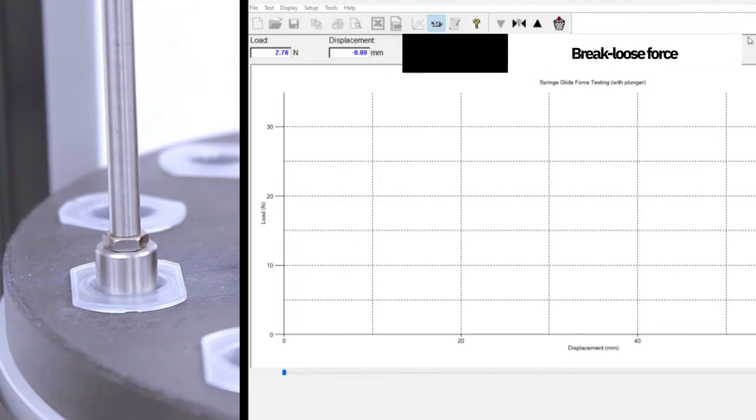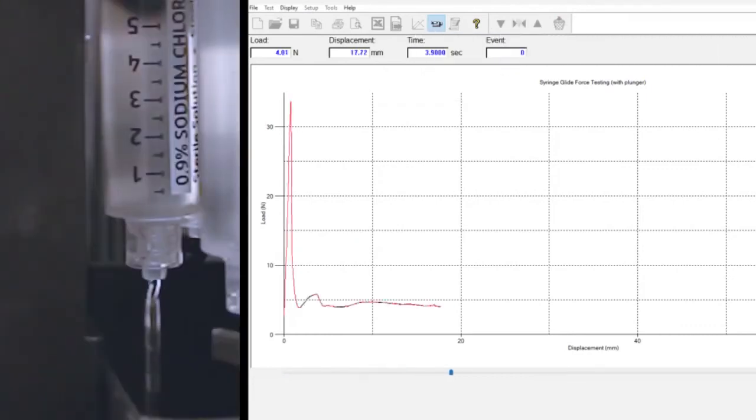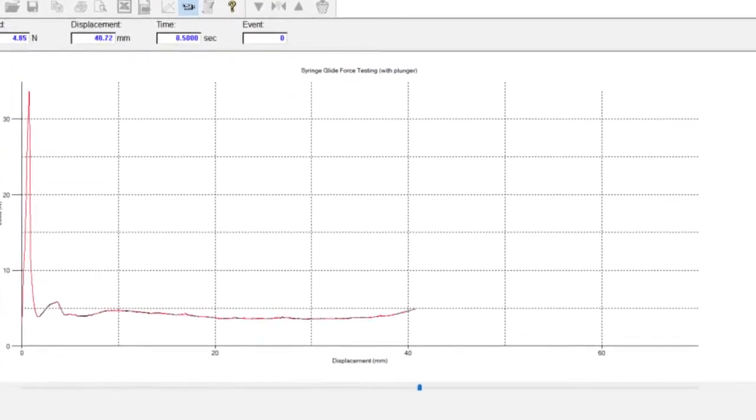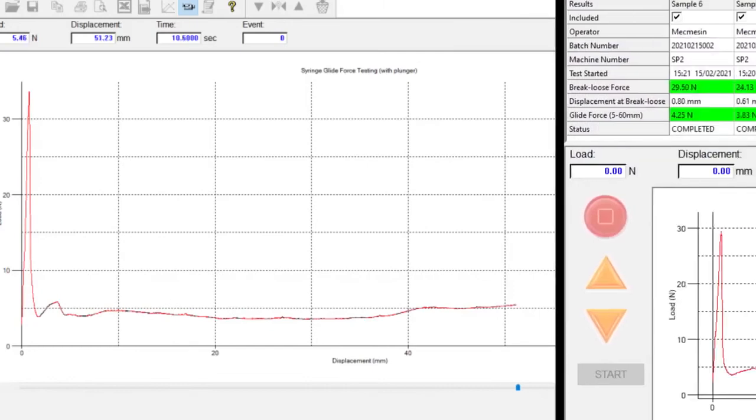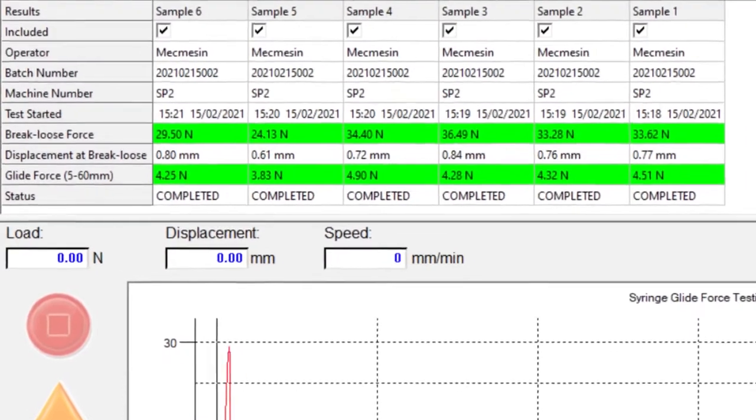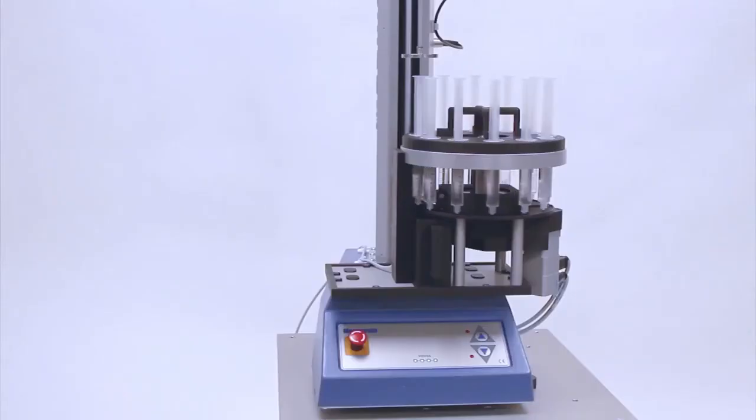Approaches the top of the syringe, touches on lightly and sets a reference point for the test. Compresses the plunger rod by a set distance and measures the forces it exerts. And finally records those all-important break-loose and glide force results with a pass-fail indicator based on the specifications laid down.